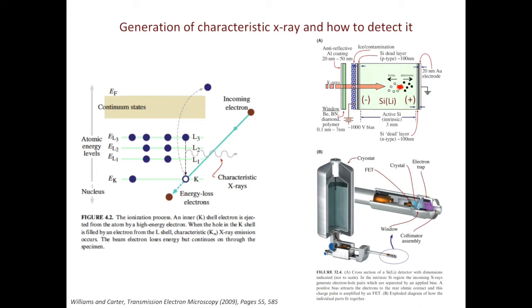There are two reasons to reduce the detector temperature. First, it will reduce the thermal excitation, so it will reduce the background noise. Second, there's lithium in silicon. At lower temperature, it also reduces the diffusion of lithium, especially outward. There's one fun fact: the lithium-doped silicon detector is also called the silly detector.